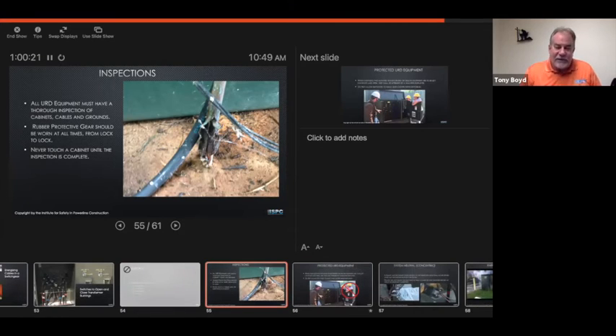This was actually in a switch gear, and that switch gear that I showed you earlier, this was the ground rod that was down in there. I got a good close-up picture of it. We actually had a ground rod on the other side of this piece of equipment that gave us a good grounded bond, so I wasn't that worried about it, and they were all tied together. We actually opened up this part of the switch gear. I saw this and I asked the question. We had 15 people on site. I asked the question, okay, have we inspected this transformer, this switch gear? And all 15 said, oh, yes, we've been in here. As a matter of fact, we were in here just last week.